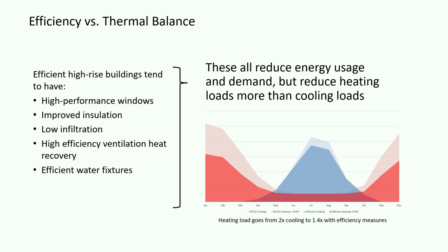You'll notice at first we have about twice as much total annual heating as we have in our cooling. And then when we're done with that, our difference is only about 40%. So, as we say, our concern is with cooling dominance. You still have 40% more heating. What's the problem?